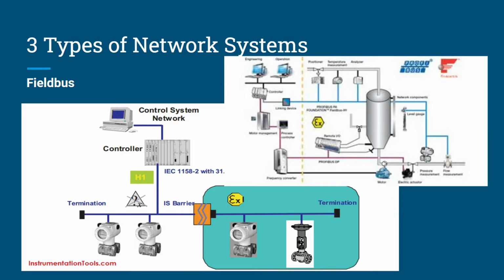The fieldbus links the programmable logic controllers of the direct control level to the components in the plant at the field level, such as sensors, actuators, electric motors, consoles, lights, switches, valves, and contactors, replacing direct connections via current loops for digital input and output signals. The requirements for a fieldbus are therefore time-critical and cost-sensitive.